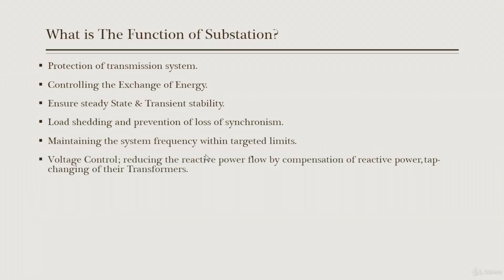For example, the system frequency in Egypt is 50 Hz. We can control the frequency between 50 and 50.5 Hz as a maximum, or down to 49.5 Hz as a minimum. If the frequency exceeds or drops below these limits, devices inside the substation start working to maintain the frequency within the target range. The substation also contains devices for voltage control.